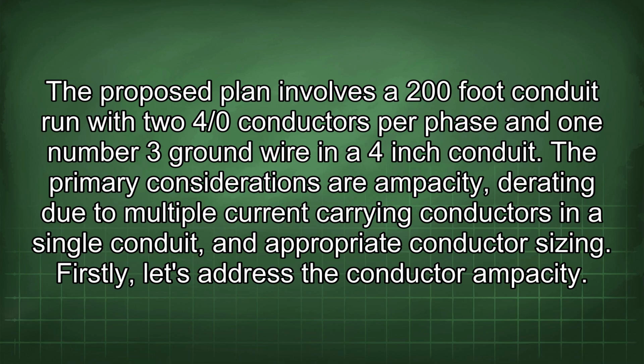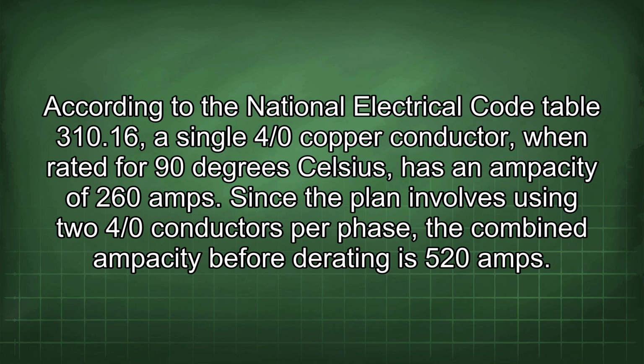appropriate conductor sizing. Firstly, let's address the conductor ampacity. According to the National Electrical Code Table 310.16, a single 4/0 copper conductor, when rated for 90 degrees Celsius, has an ampacity of 260 amps. Since the plan involves using two 4/0 conductors per phase, the combined ampacity before derating is 520 amps.